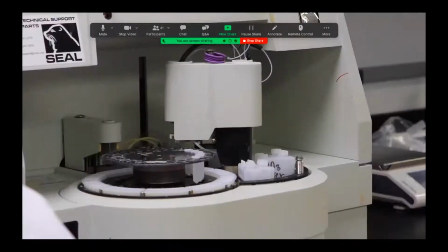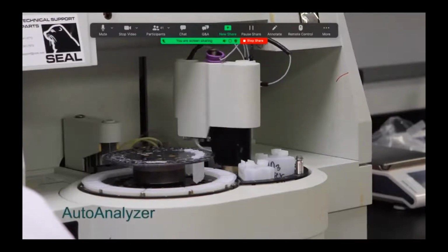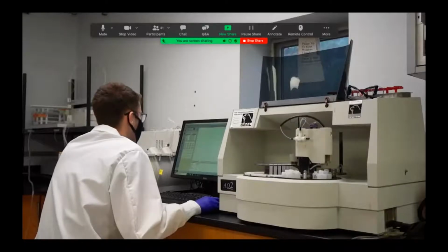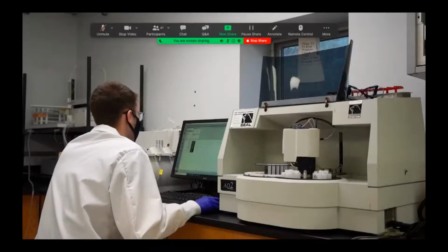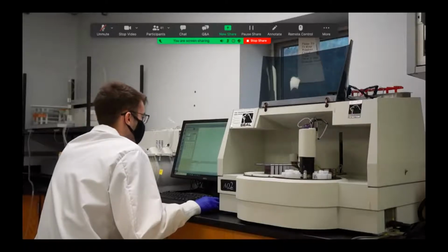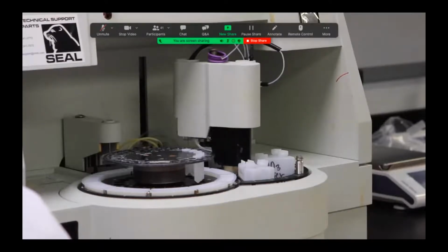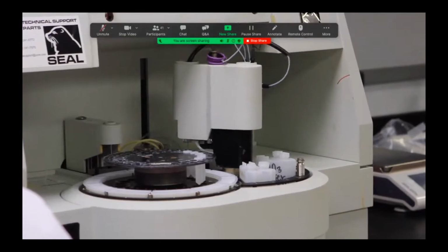This instrument is called an autoanalyzer and is used to measure concentrations of dissolved chemicals such as phosphate, nitrate, and ammonia. We run these tests on several thousand samples each year. The whole process is automated for rapid, precise, low-cost analysis. Chemical reagents are added automatically to samples and form uniquely colored complexes. The instrument measures the intensity or absorbance of the color to quantify how much is present.